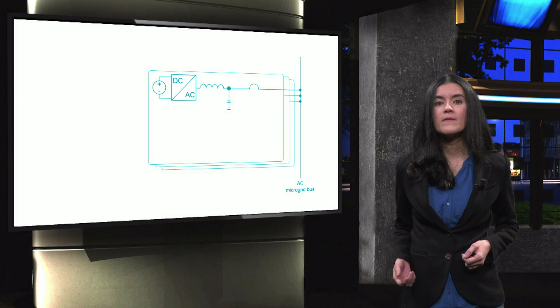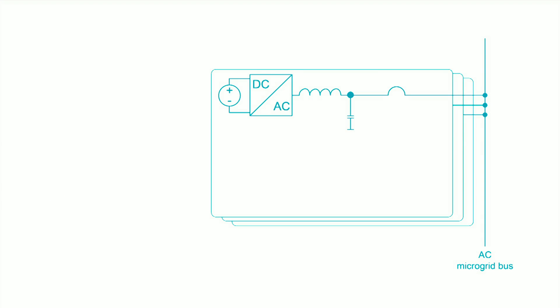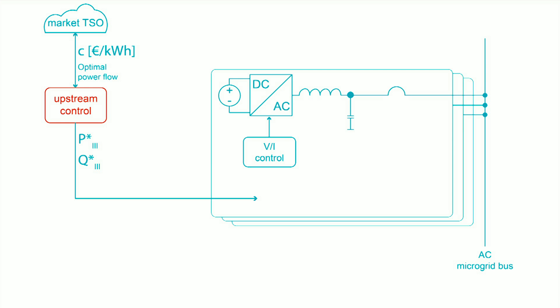Here, we can see an example of the implementation of hierarchical control in a distributed generation system. Local control acts on power electronics interfaces that connect generators, loads and batteries to the microgrid bus. The control that acts on the power converter here, a DC to AC inverter, is based on voltage or current. On the very high level, upstream control provides the unit with active and reactive power setpoints, considering market and price signals retrieved from the transmission system operator, or TSO, or the distribution system operator. At this level, control is responsible for the optimal power flow in the microgrid.